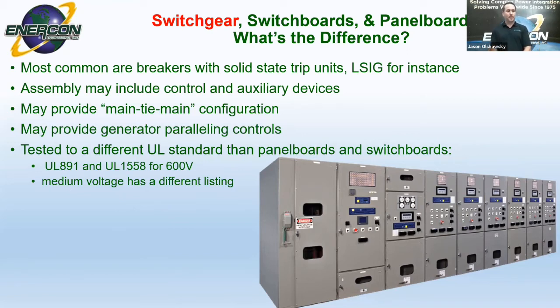Switchgear can also be set up for different UL standards, more so than panel boards and switchboards. In low voltage switchgear, we'd be looking at UL 891. And so that would be dead front switchgear and low voltage. And UL 1558 for 600 volt. Medium voltage switchgear also has a listing of UL metal clad switchgear. So that they all follow specific guidelines for the equipment used, and so each part and piece part within that switchgear would carry a UL recognized label.